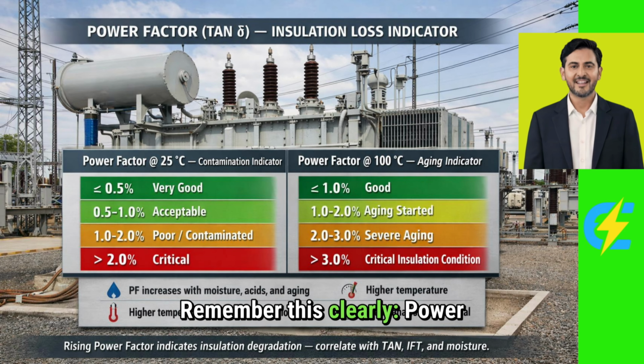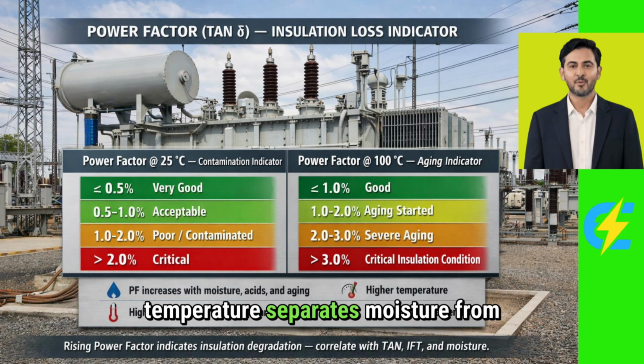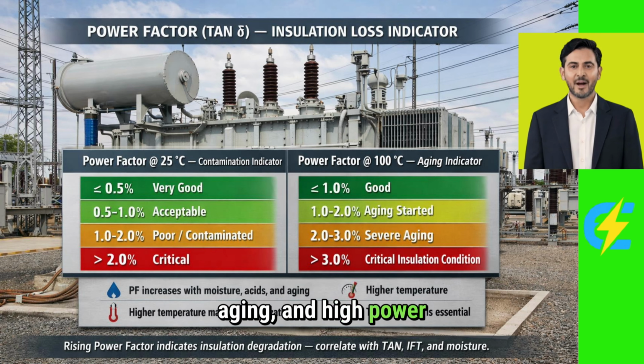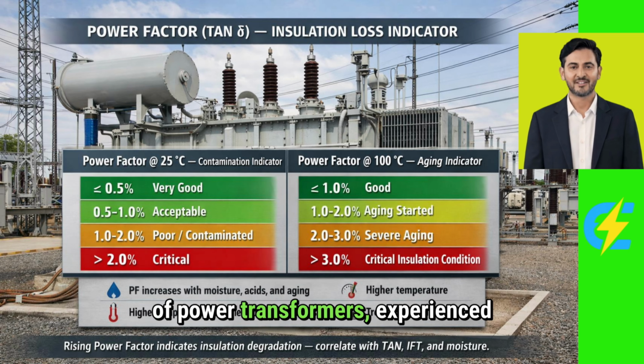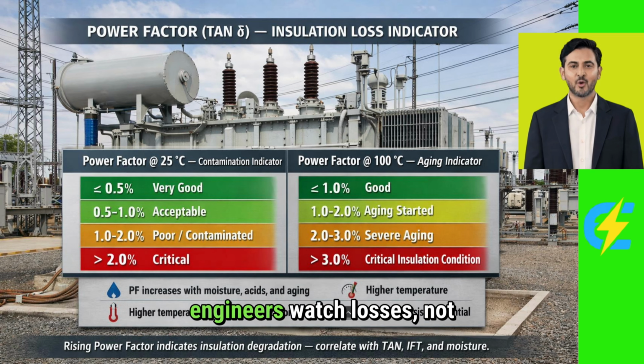Remember this clearly. Power factor shows dielectric losses, temperature separates moisture from aging, and high power factor at 100 degrees means oil life is ending. This test is not optional for serious transformer maintenance, it is essential. Because in the world of power transformers, experienced engineers watch losses, not just strength. And power factor is your window into those losses that could spell the difference between reliable operation and unexpected failure.